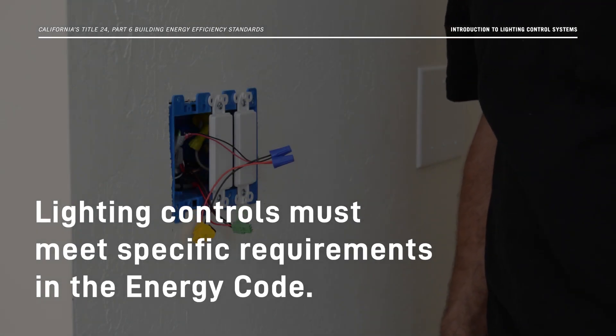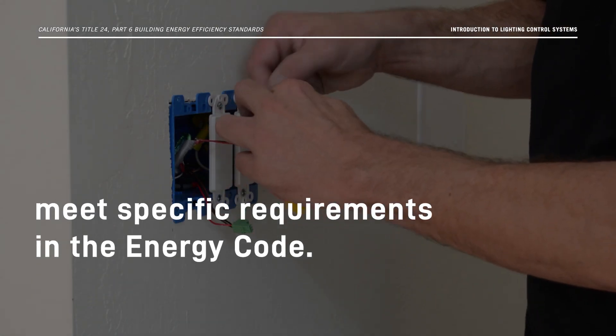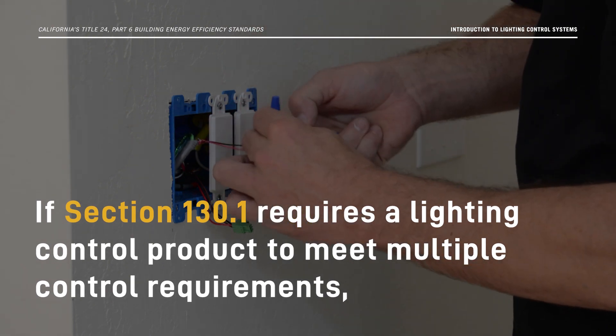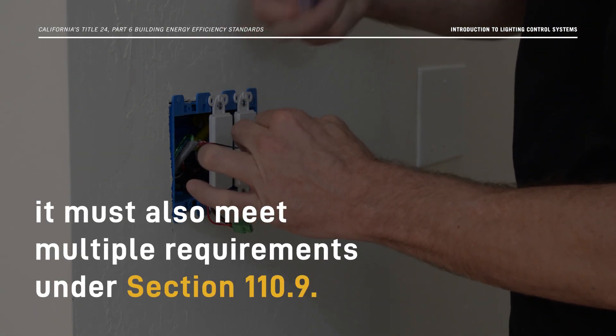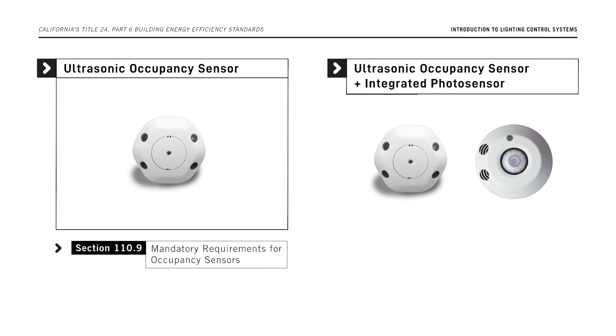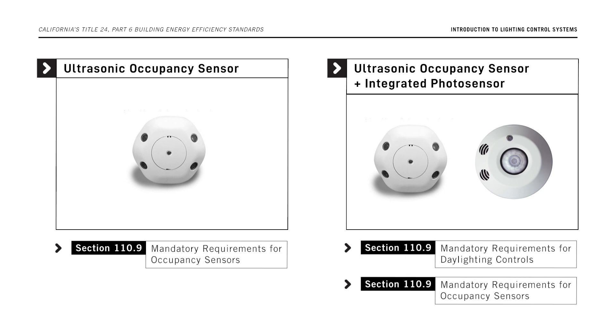Lighting controls must meet specific requirements in the Energy Code. If section 130.1 requires a lighting control product to meet multiple control requirements, it must also meet multiple requirements under section 110.9. For example, if an ultrasonic occupancy sensor is installed to comply with the shut-off control requirements in the Energy Code, then it also must comply with the specific device requirements in section 110.9. If that same device contains an integrated photosensor to serve as part of a daylighting control system, then it also needs to comply with requirements for a daylighting control contained in section 110.9.